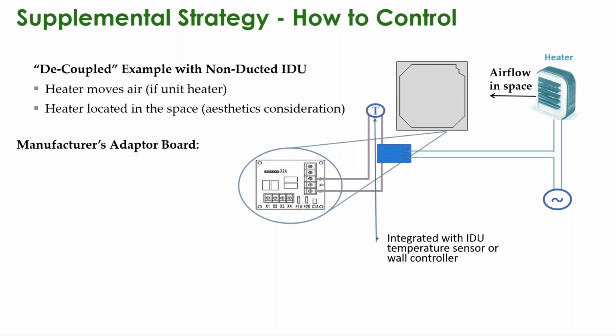a small unit heater if aesthetics allow for it, baseboard radiators, either electric or hot water. Any of those items can be triggered on in the same strategy that you would use for an electric heater in the duct. Same rules are going to apply. It's either a field installed accessory board added to the unit or points on a fan coil that can be programmed for the dry contacts to act.